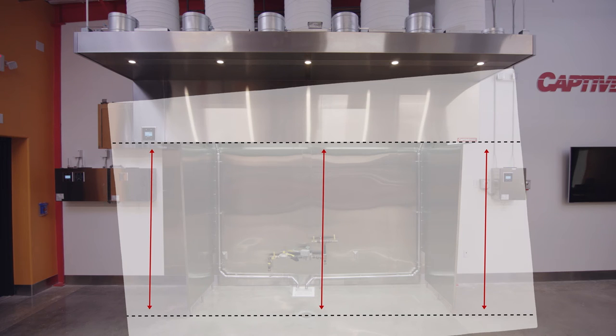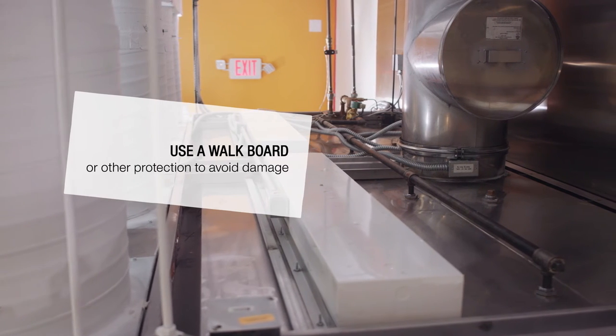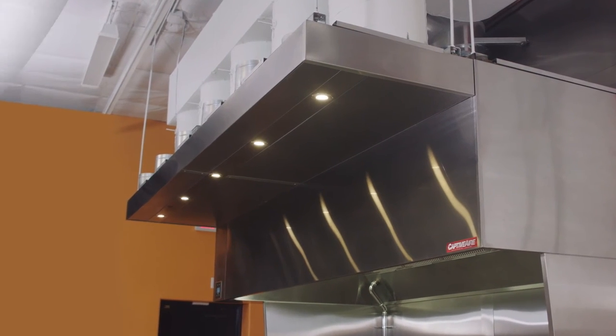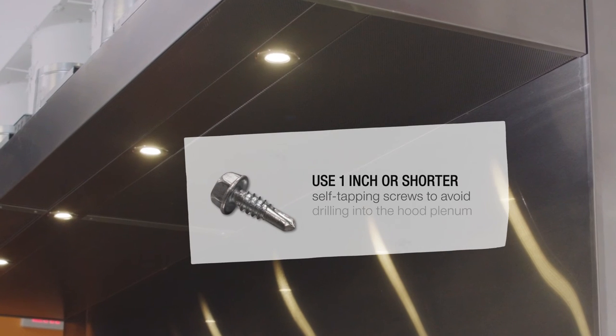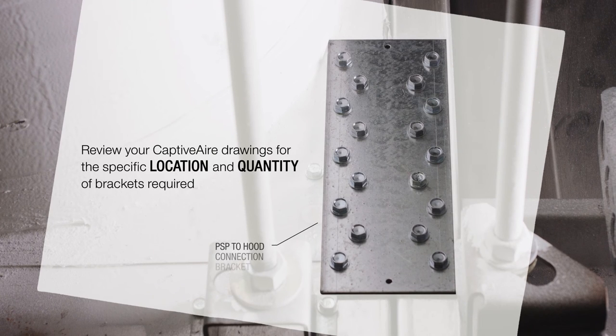Check your CaptiveAire installation drawings for the specific height the hood should be above the floor. The makeup air plenum can now be hung into place using high-quality threaded rod. The plenum should also be fastened to the hood using self-tapping screws. Don't forget to install the PSP-to-hood connection brackets at the top of the hood and plenum; these brackets should also be installed using self-tapping screws.